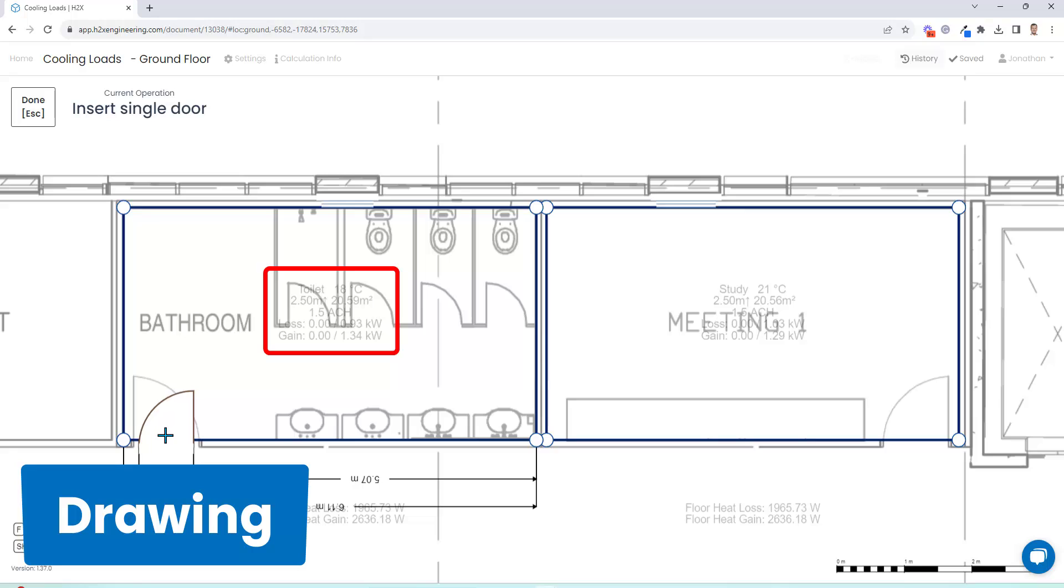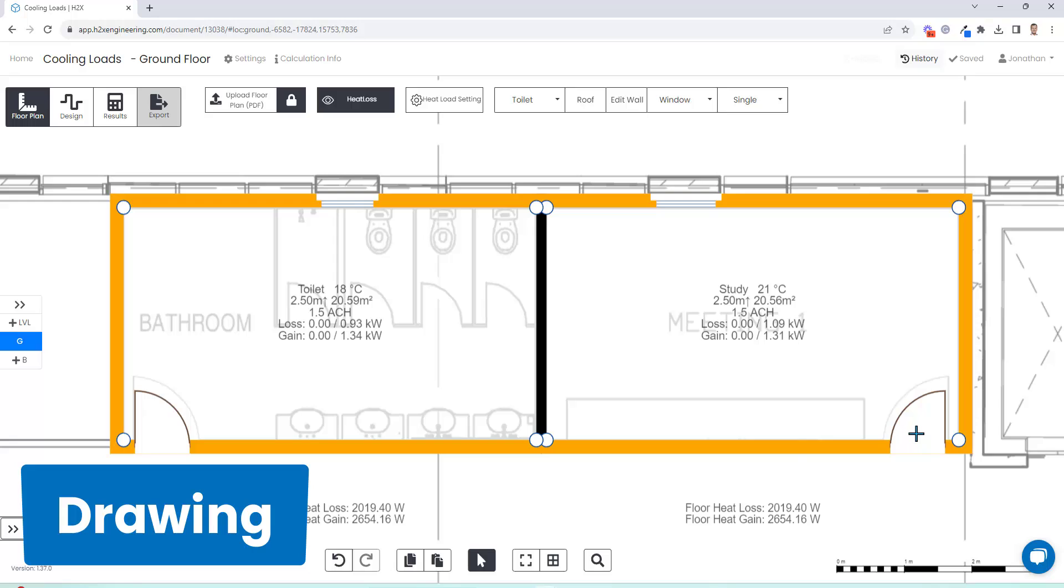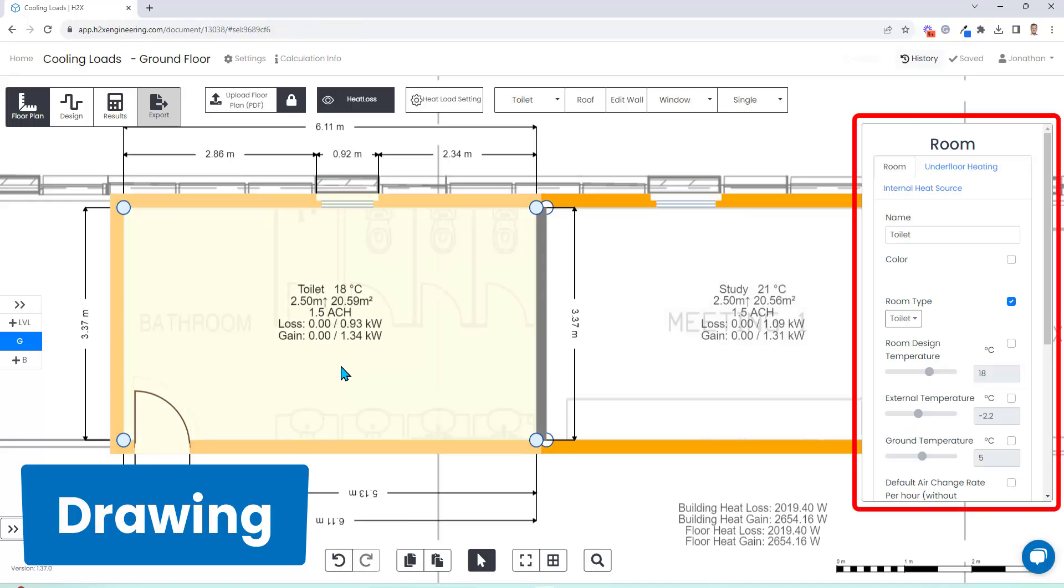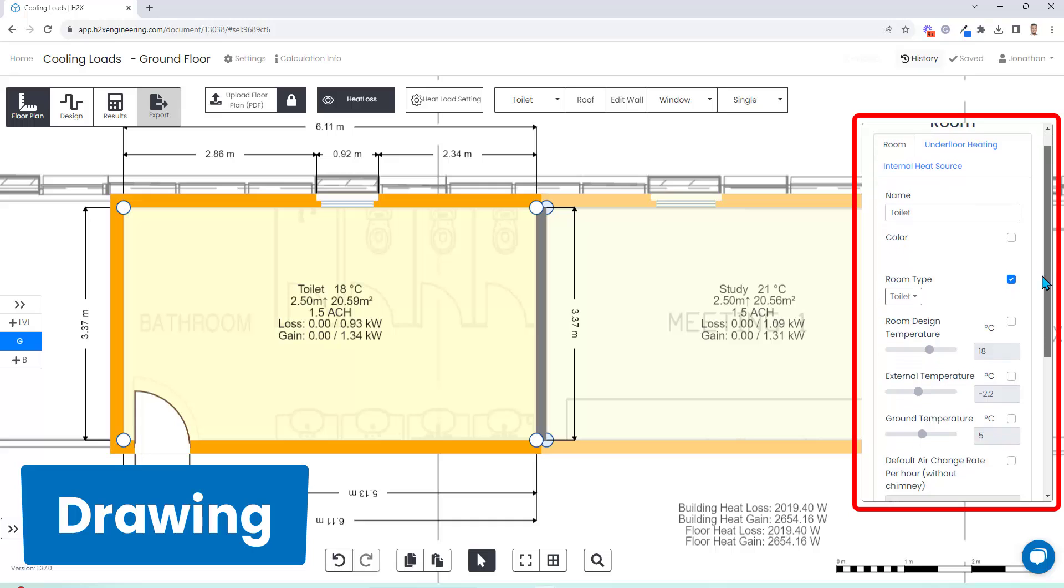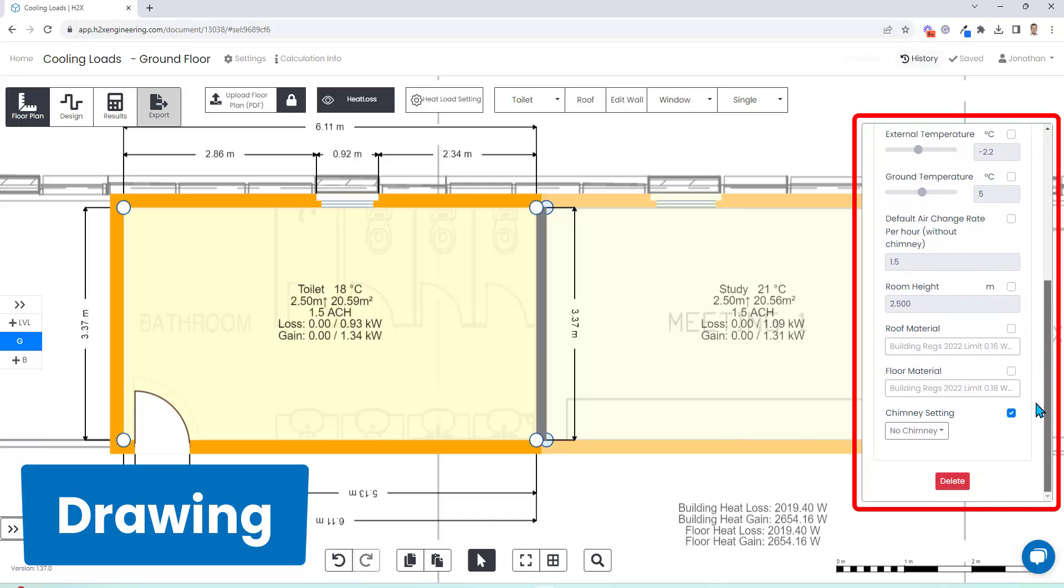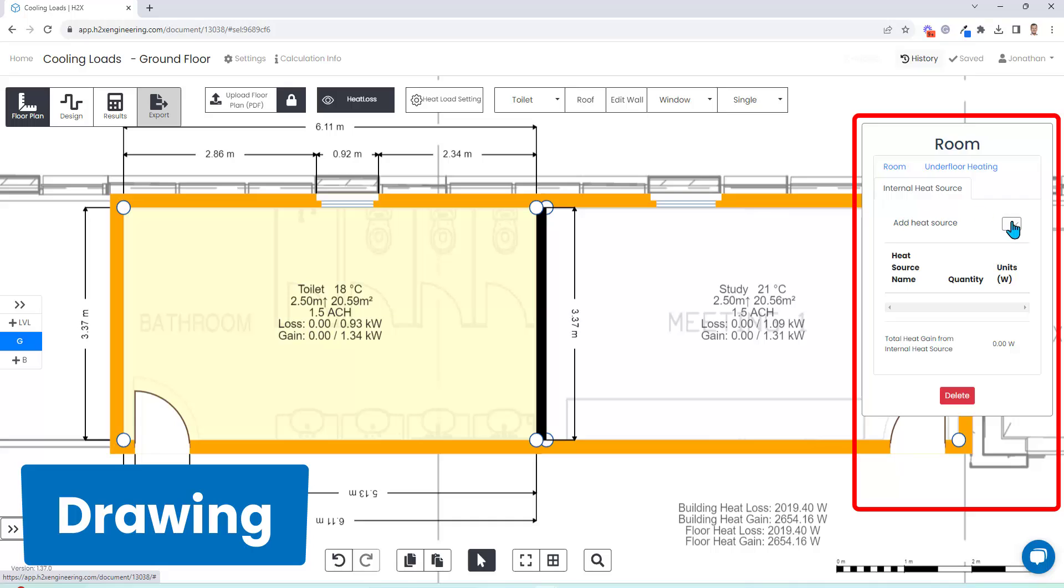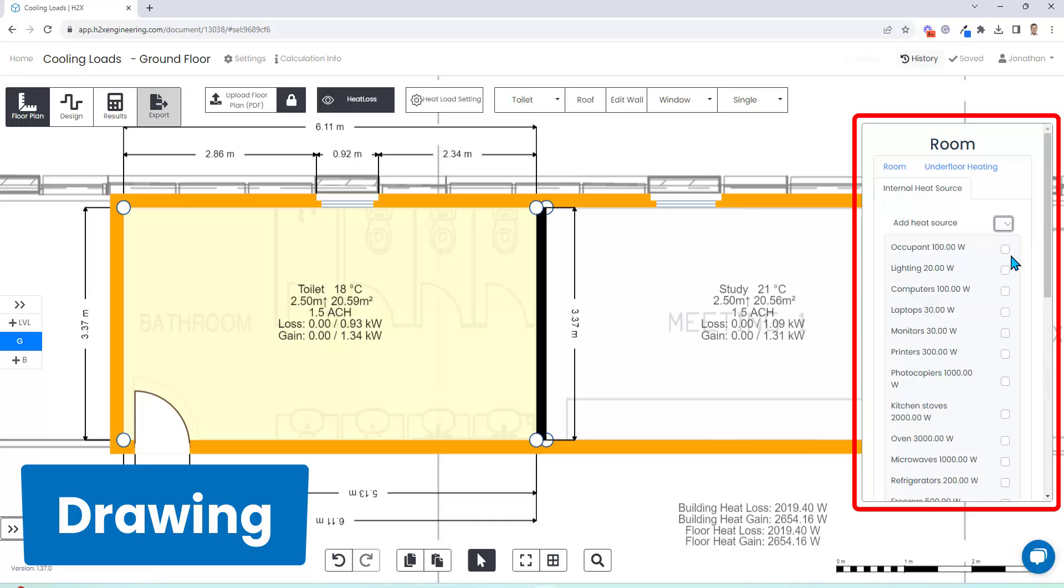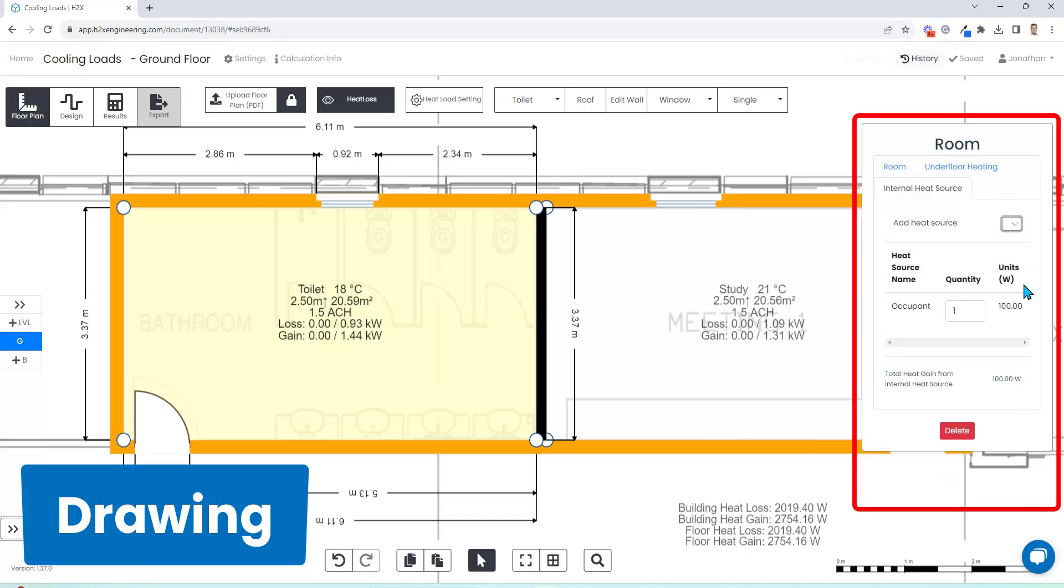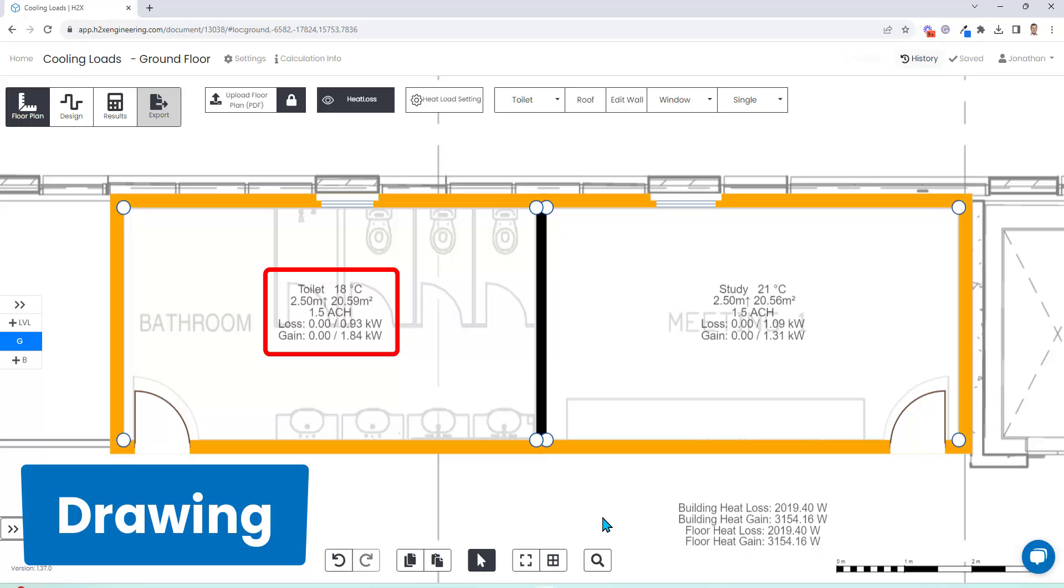If you ever want to override the defaults of a room, you can click on it and change things like the name, the temperatures, the number of air changes, the materials that are being used, and you can also add internal heat sources. So here where we have 1.34 kilowatts of heat gain, if we choose to add five occupants at 100 watts each, that goes up to 1.84 kilowatts.